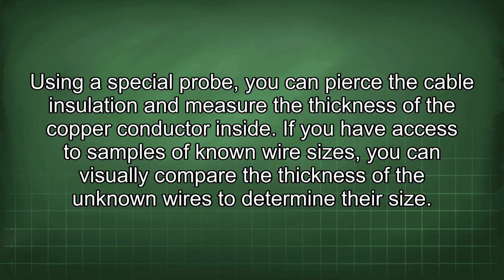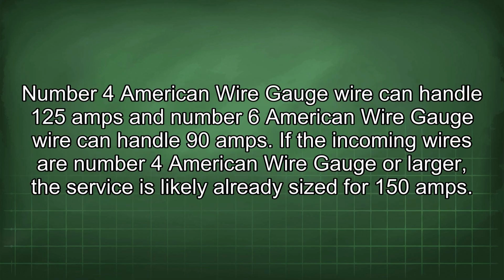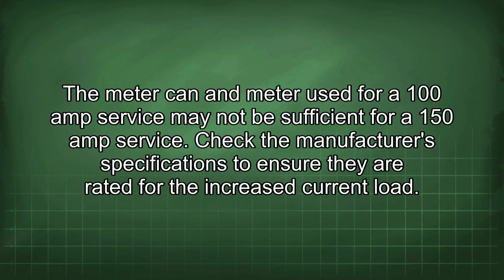to determine their size. Number 4 American wire gauge wire can handle 125 amps and number 6 American wire gauge wire can handle 90 amps. If the incoming wires are number 4 American wire gauge or larger, the service is likely already sized for 150 amps. The meter can and meter used for a 100 amp service may not be sufficient for a 150 amp service.